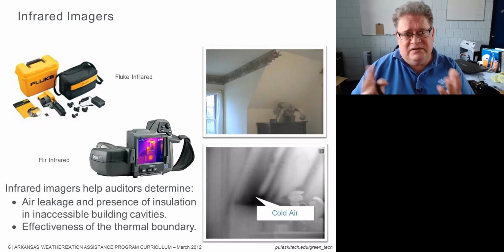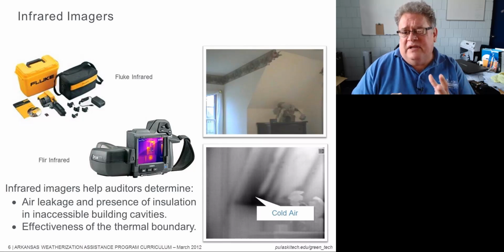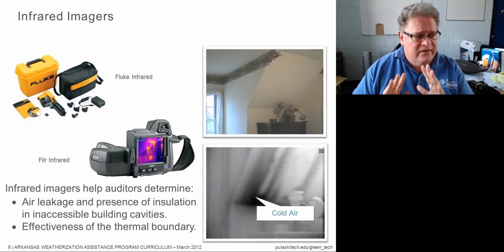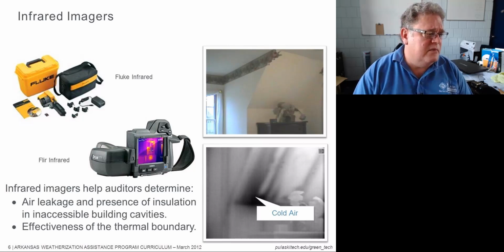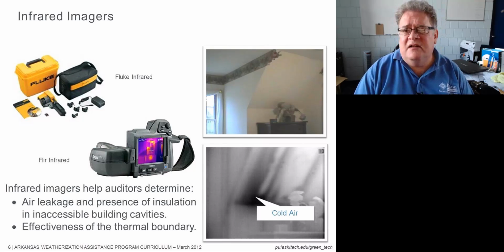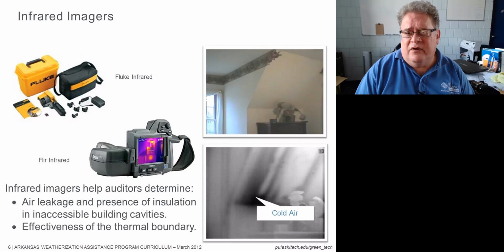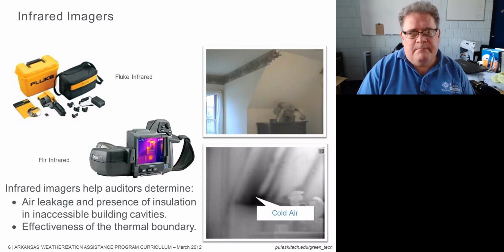Now notice how I'm saying I would suspect. I'm a level 1 thermographer, but even at that, I'm not going to make assumptions and say, well, that's what this is. Because until we test, we don't know. We can just see and then interpret what we see. That's the biggest thing with infrared. Always remember that it's always an interpretation of what you're seeing. It's not a hard, fast rule. Those black streaks there, in my mind, warrant a lot of investigation. We need to figure out why we have that. Get into that attic section, that sidewall attic over there, and figure out that side attic, and find out why we have apparent air movement there and confirm it with smoke or something else.